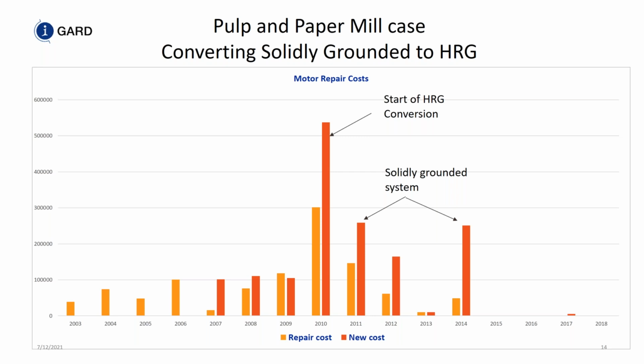In this particular facility, we changed 100 substations from solidly grounded to resistance grounded, solely as an arc flash mitigation technique. But what they found is in 2010, they started changing over, and they had more systems that they switched over in 2011, 2014, but more damage occurred in the solidly grounded systems before they were damaged, and the high resistance grounded systems had very little damage, and this is seen by the magnitude of the motor repair costs in the system.